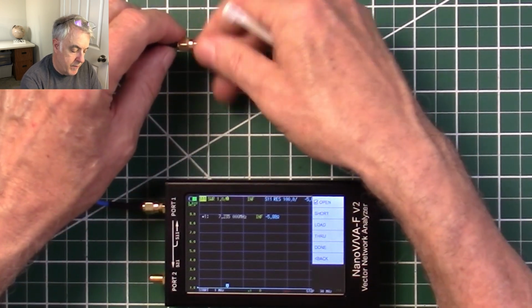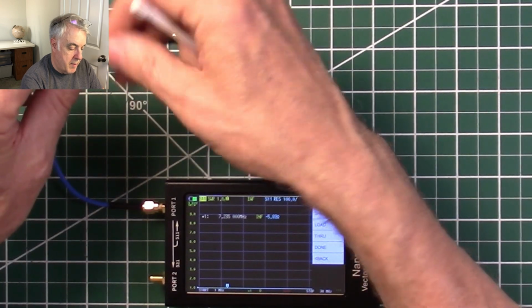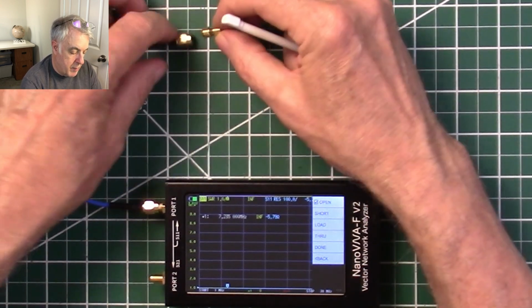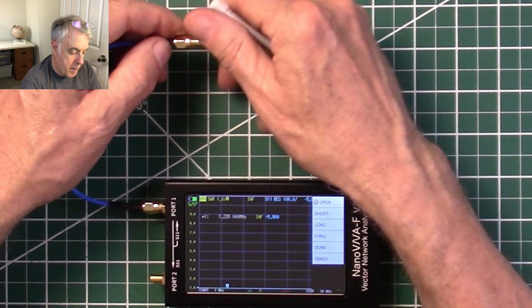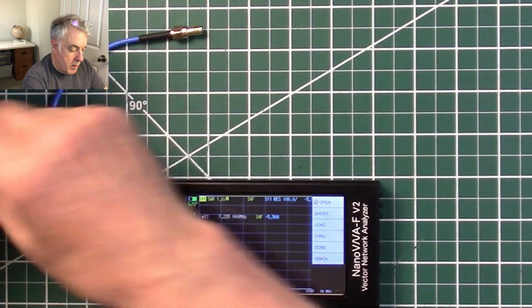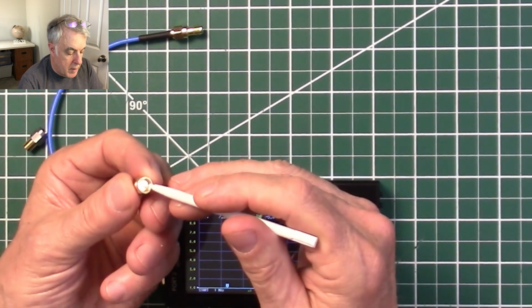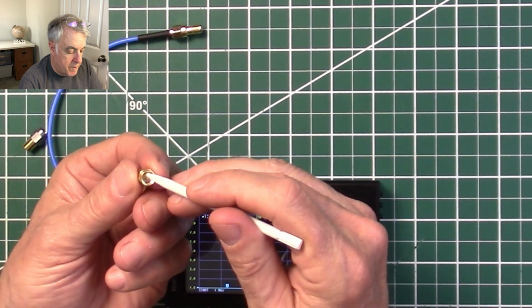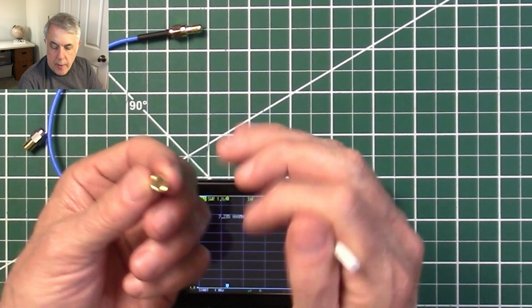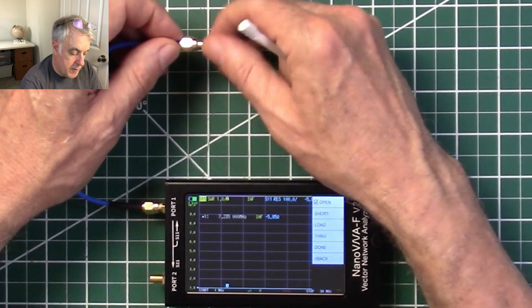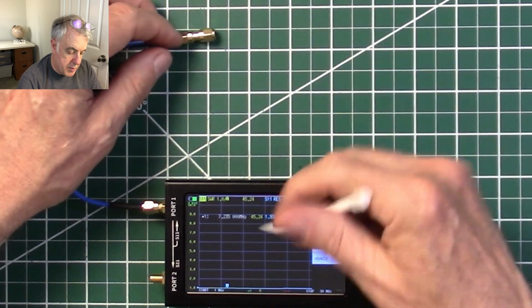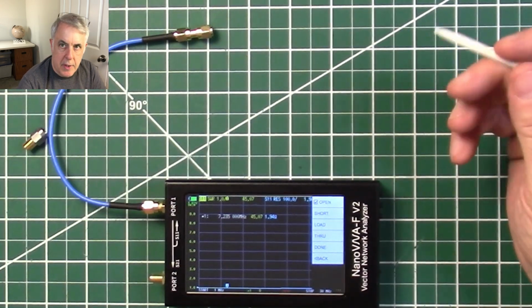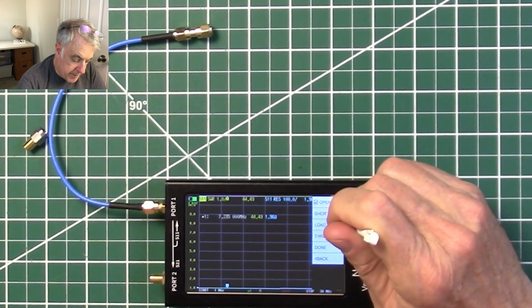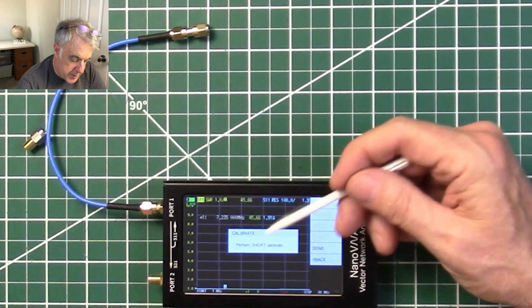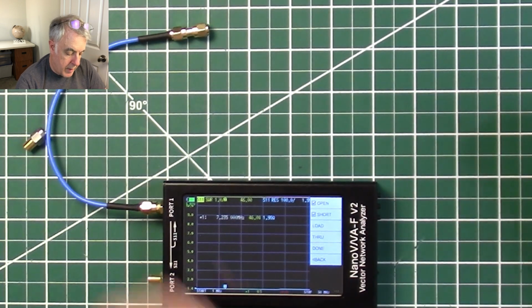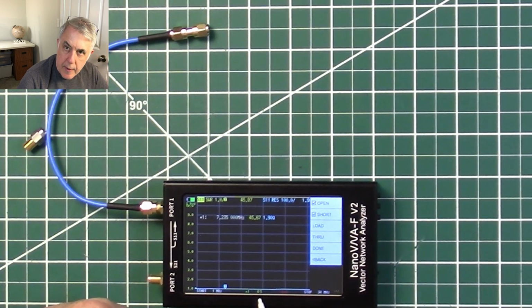So we take off the open. I didn't mean to unscrew the double female, but that happens sometimes. Put it back in. And this is the short. You see it has that pin there in the center. And that connects directly the pin to the shield, the center conductor to the shield. And you can see those traces pop up as I'm connecting and disconnecting these different calibration devices. So let's go to short, click on it. It's performing the short calibrate. Okay, so we're calibrated for short. You can see the S down here that it's calibrated for short now.